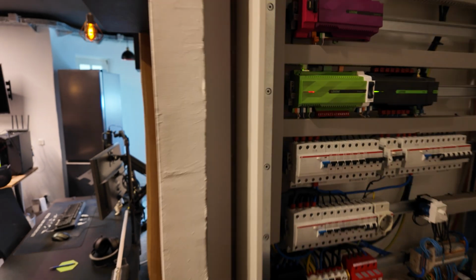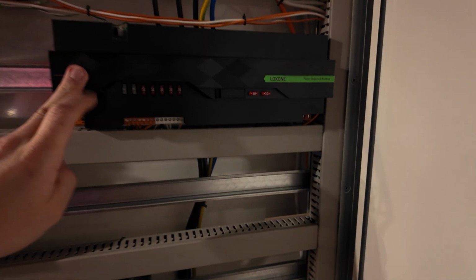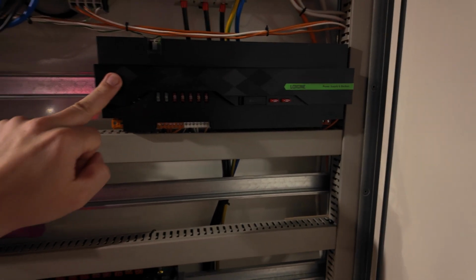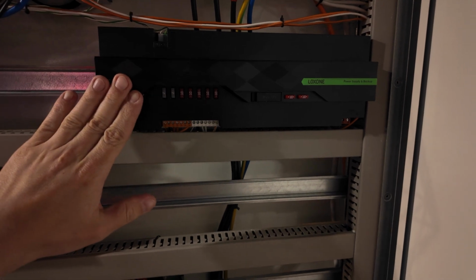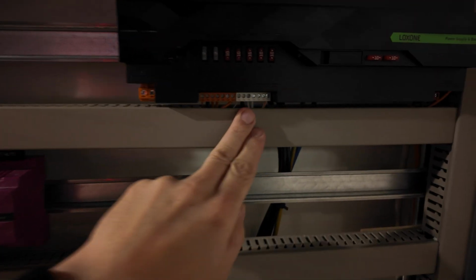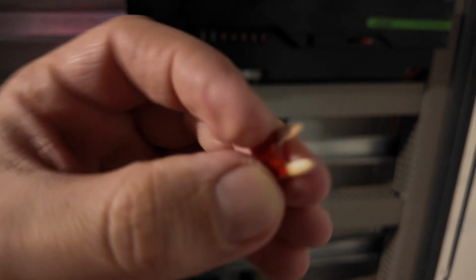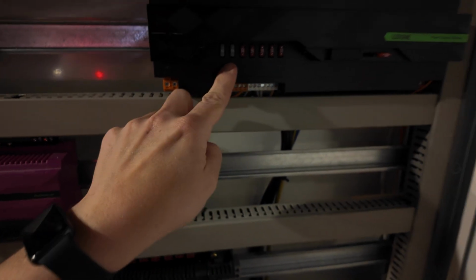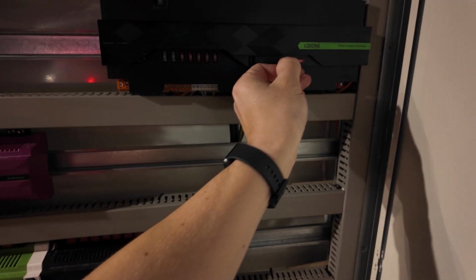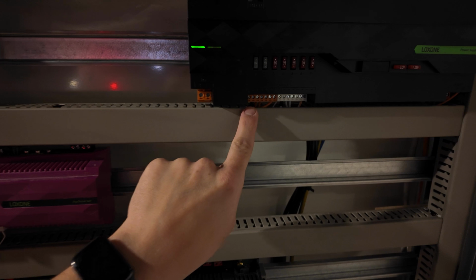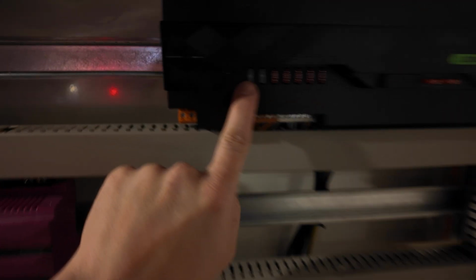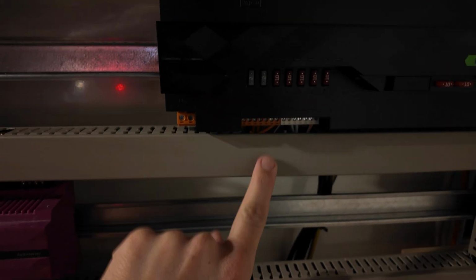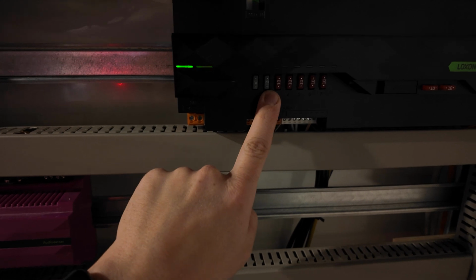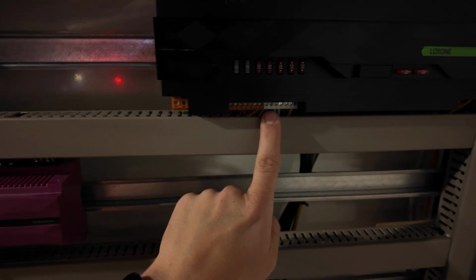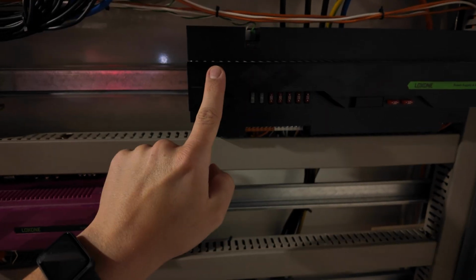In the office cabinet, I am using the Loxone Power and Backup, which is super powerful, 40 ampere on 7 channels, which have these little fuses, as you might know, already built in, so you're also safe on the DC side. Here I'm always using the first channel for the mini server and its extensions with 2 ampere, the next channel for the push buttons and presence sensors, and then you have 4 more outputs for, let's say, dimmable channels, the music, whatever else you have.